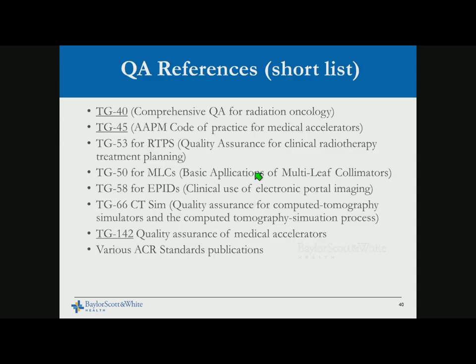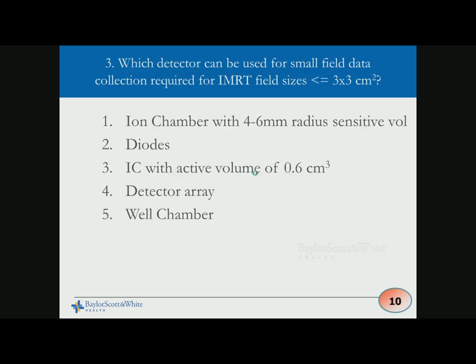Putting it all together, there are many QA recommendations to go through at acceptance testing. Since there are no clear acceptance testing tolerance guidelines, we must rely on periodic QA recommendations from various task groups. For example, a respiratory gating system added to your LINAC requires going through its dedicated task group report. This is a very short list of task groups one has to actually go through.